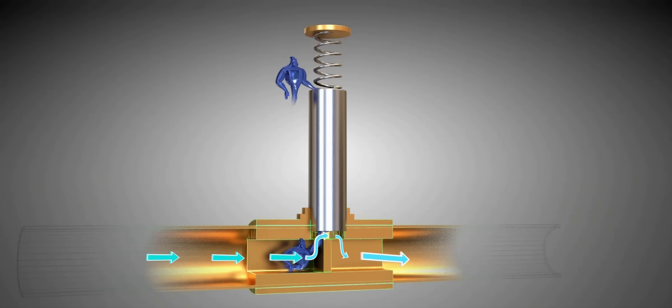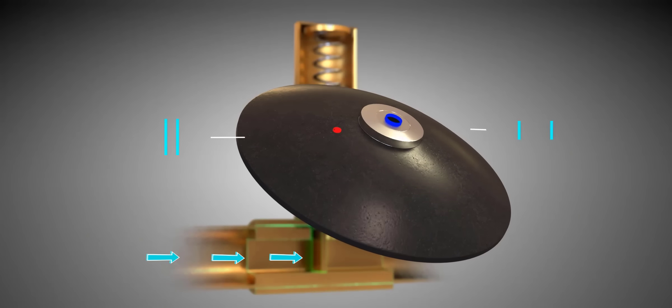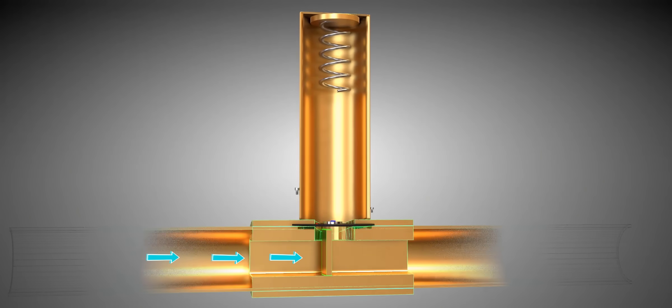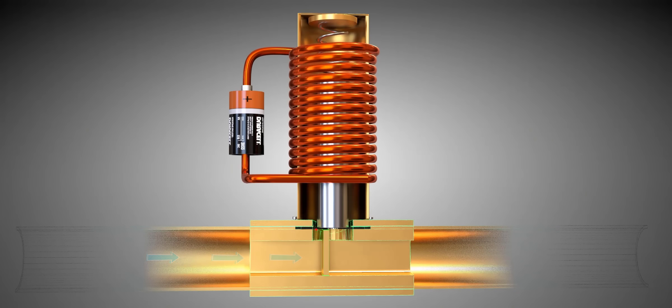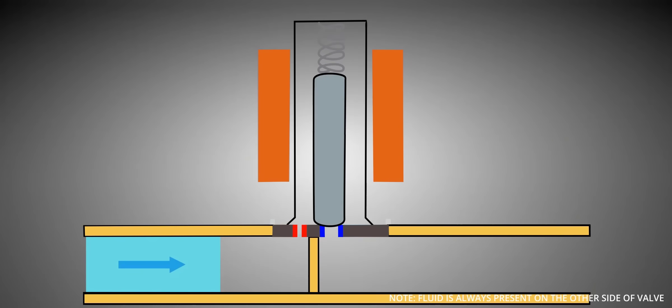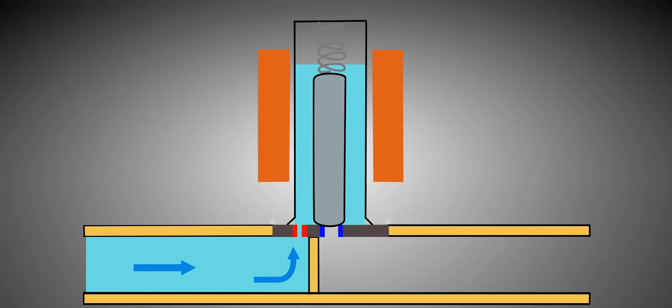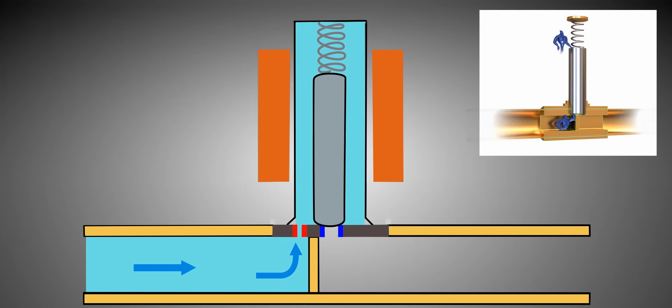The engineers came up with a perfect solution. Just keep the same fluid pressure on both sides of the armature. Let's see how this new design is achieved practically. The design engineers used a flexible rubber diaphragm with two holes. This diaphragm is screwed with the valve body. The closed condition of the valve is shown. The tiny red hole on the diaphragm plays a major role here. You can see how the fluid reaches both sides of the armature due to this hole. This means that when the valve is closed, the fluid pressure acting on the armature gets cancelled. This perfectly solves the previous problem.